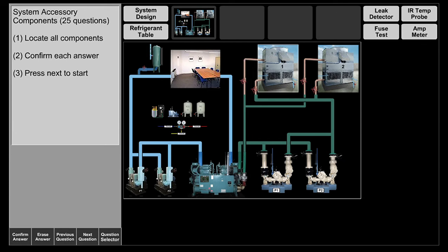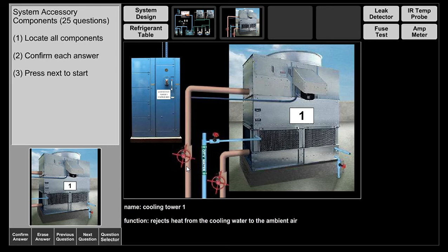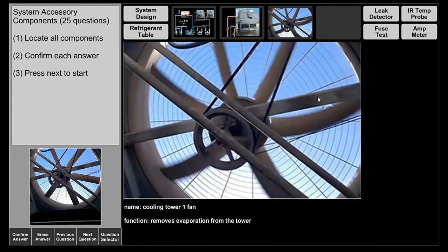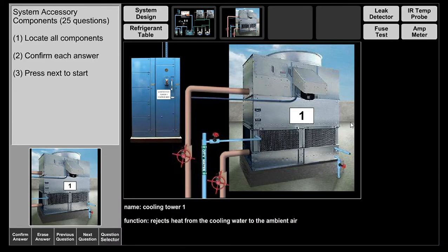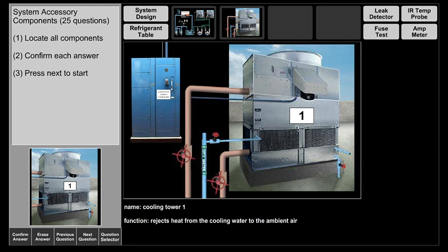This 85-90 degree water is brought all the way up to the roof into the cooling tower. The hot condenser water goes to the top of the fill, and the fan circulates outside air through the fill. As the air passes through, it picks up all the heat the water absorbed from the condenser, and this heat evaporates and is discharged at the top of the tower — which is why you see cooling towers on rooftops with what appears to be white smoke in winter, which is simply the temperature difference.